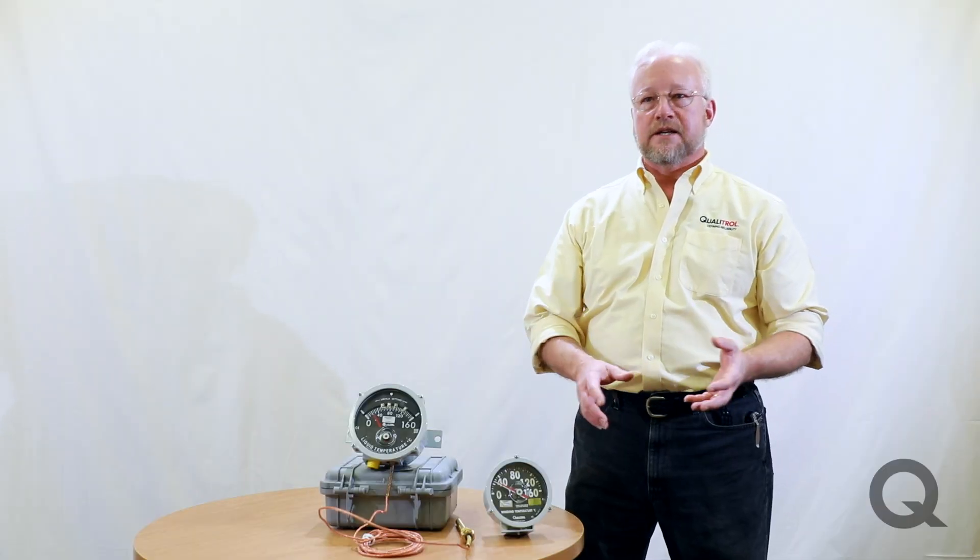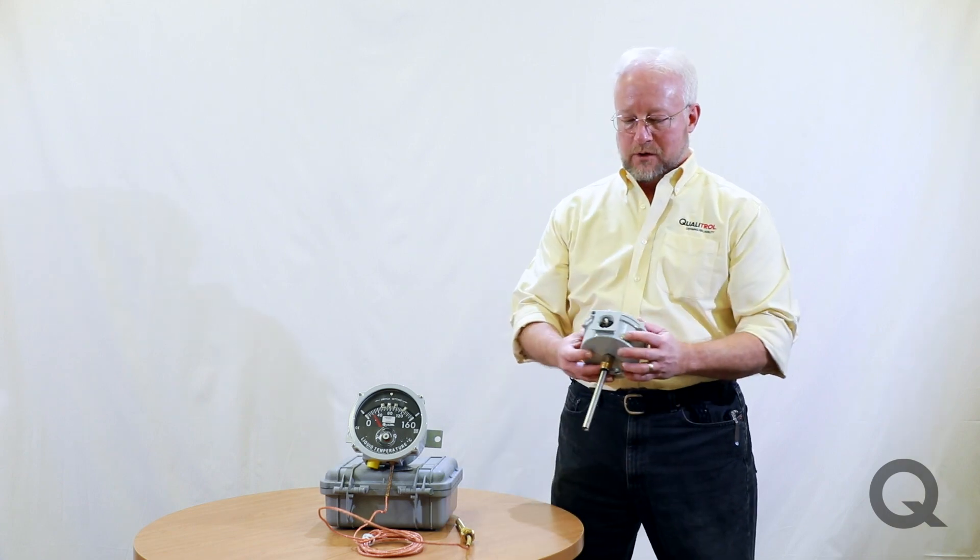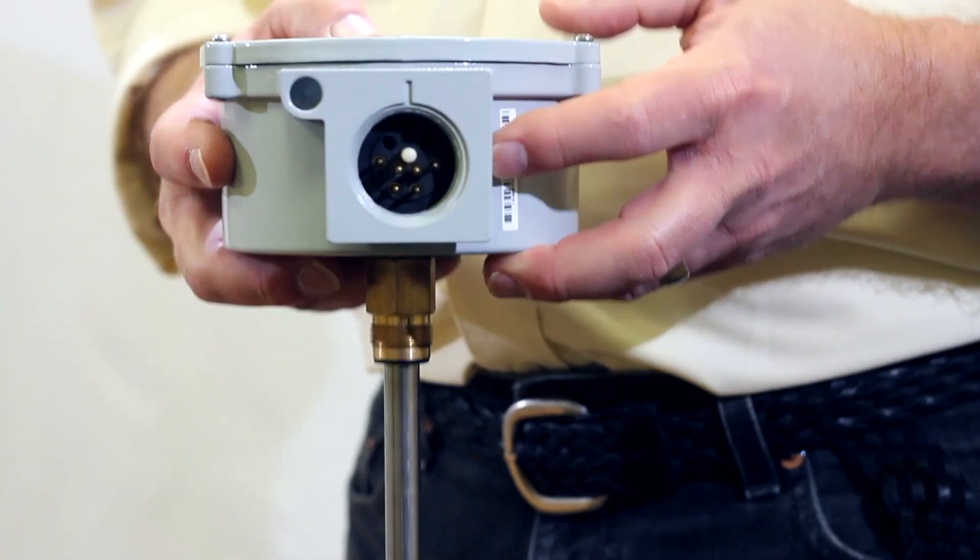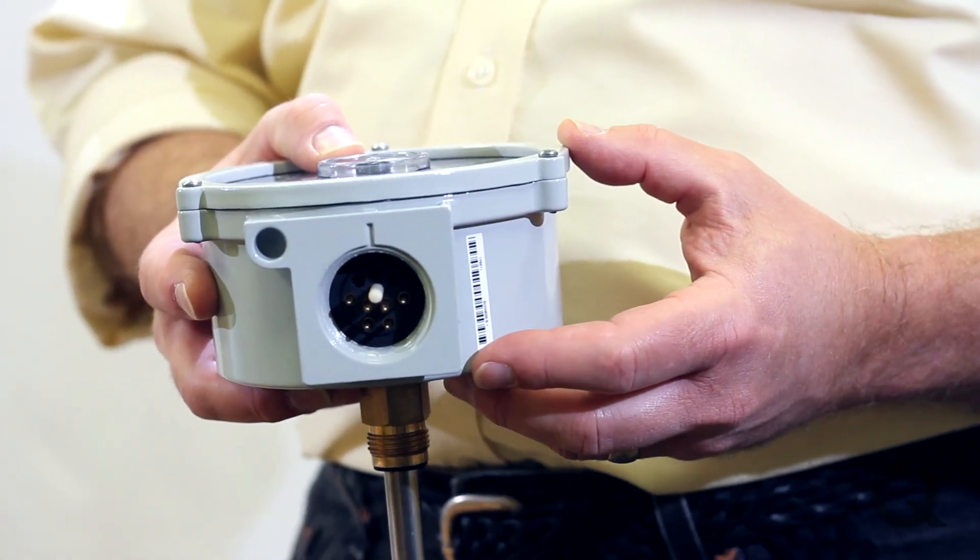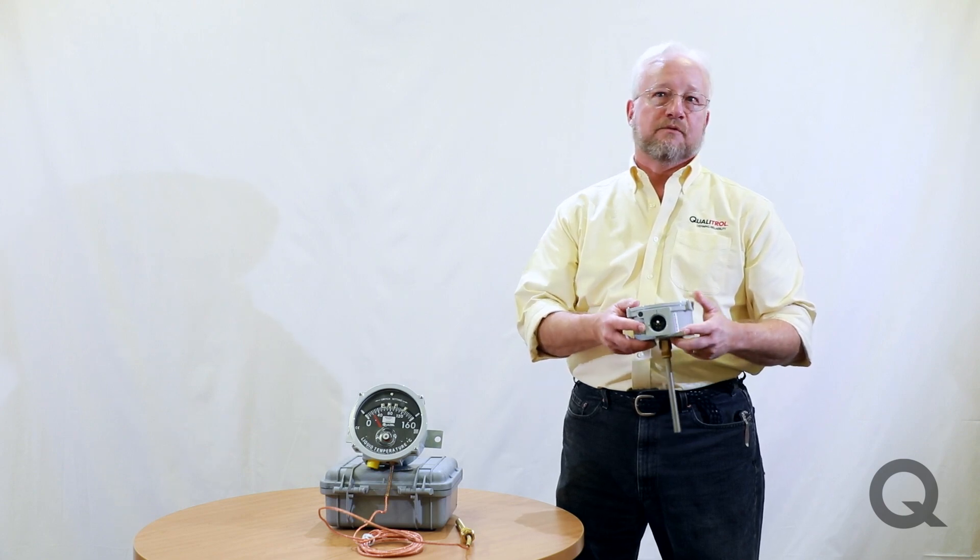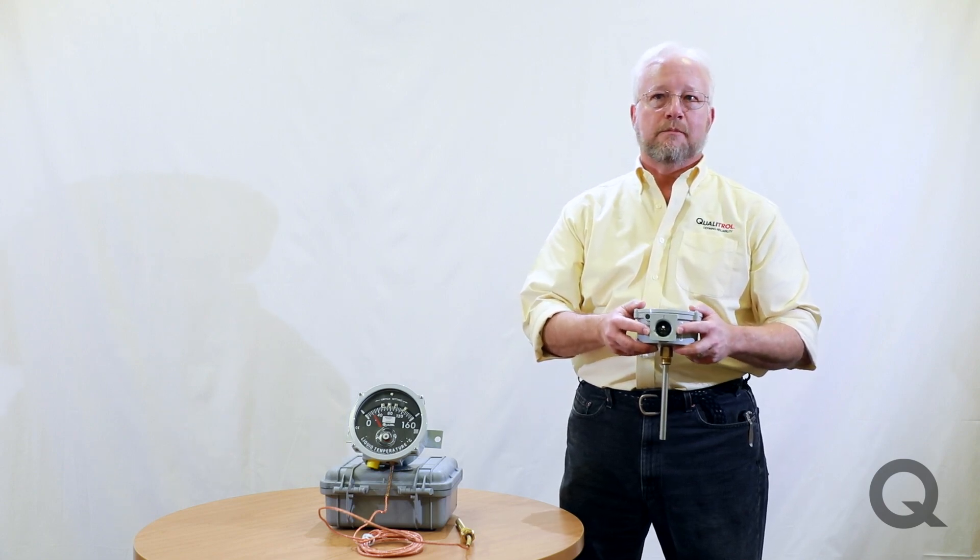And then the actual way to tell whether you've got form A or form C is you look at the bottom of the connector output and you can count the pins. If you've got one switch and you've got two sets of pins, then that's form A. If you've got three sets of pins, that's going to be a form C.